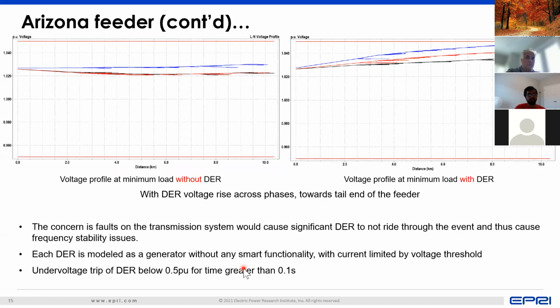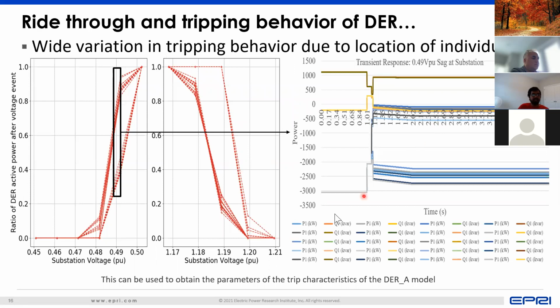So for the study that we did in Arizona, you see the voltage profile at minimum load without DER and the voltage profile at minimum load with DER, there is a distinct rise in voltage profile because inside the distribution feeder, there is generation coming about, so the net load is decreasing. Lower the load, the higher the voltage profile. And the concern is that if there are now faults on the transmission network, will those DER be able to ride through or not? So as part of our detailed studies, we see that there's a wide variation of tripping that can occur due to the location of the individual DER. This was something that we saw in the previous slides also, that for a given level of voltage, you could either have only 20 to 30% of the DER that comes back after the event, or you could have close to 95% of DER that comes back after the event.